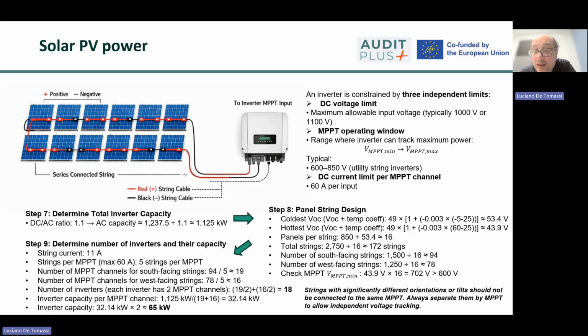Cold temperatures increase voltage and warm temperatures reduce it, so both extremes must be checked. A typical design process calculates the maximum string voltage at lowest expected site temperature to ensure it does not exceed the inverter limits, and the minimum operating voltage at high temperature to ensure that it stays within MPPT range. Once the number of modules per string is fixed, multiple strings are then connected in parallel to reach the desired system capacity while maintaining electrical balance across MPPT inputs.